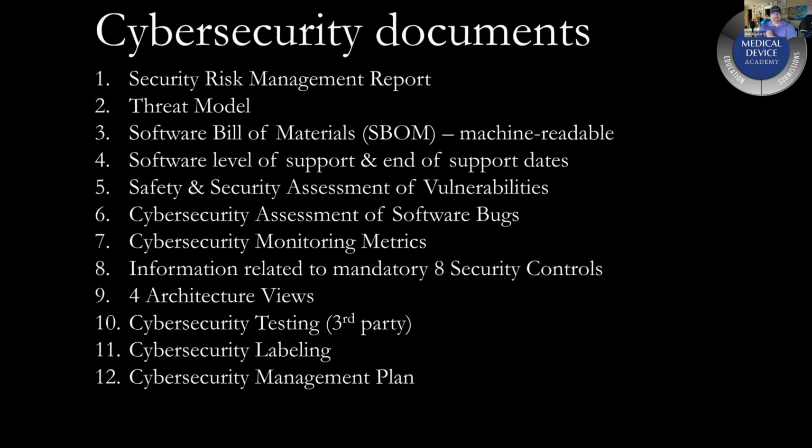And if people don't think they can hack into your software, you're sadly mistaken. They can hack into firmware. All you have to do is take off your firmware and put on their own firmware. People do that. That's why they want you to look at software in a medical device just as much. The FDA says, if you have any kind of a software port at all, a USB port or anything that can connect to the outside world, you have to provide all this testing. But a good cybersecurity firm will actually take the unit apart and look for, can I pull off an EEPROM and put on my own and make it work?